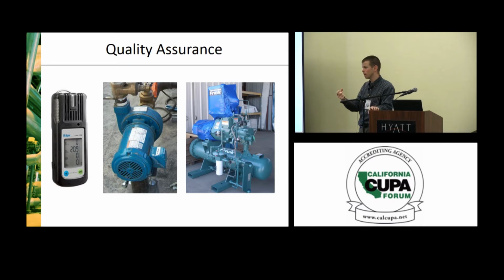It's a little gauge that has some copper in it. And we had a situation where we installed it and that little thing wasn't caught. We hadn't even started up the compressor yet, but we had introduced a little bit of ammonia gas to check rotation or something. I'm not even sure all the details of it, but it had been installed, hadn't been started up yet, and there was some ammonia gas in it. Well, just over that night, the threads corroded and it began a small ammonia leak. It wasn't a significant thing, but just something to be aware of.